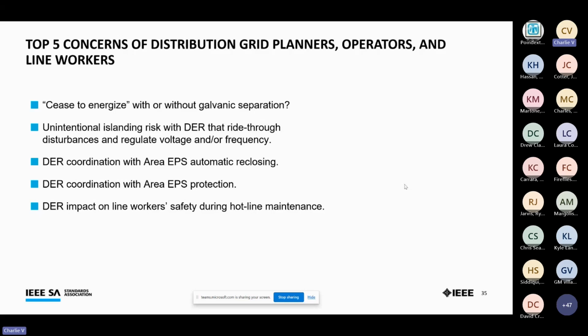And here's something to consider. If you cease to energize by disconnecting and you're 1547 compliant, the standard or default return to service is 5 minutes. There's a lot of active work already out in the West and in other areas that as DER penetration goes up, that 5 minute pause to get assets back online to serve load is impacting frequency recovery after, let's say, transmission or bulk system level events.